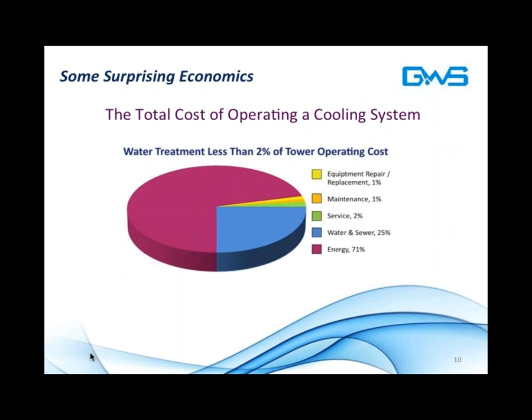You can see here that on average, water treatment costs less than 2% of the tower operating cost. So the big chunk of operating a tower in terms of cost is both water and sewer, 25% there in the blue section, and energy cost, about 71%. So we have a significant opportunity in front of us to improve the efficiency of our operating systems to cut overall cost. And that should be our focus. I would argue that every building manager and operator should make system efficiency a significant focus if they want to drive down costs. Said another way, focusing on the operating cost of chemical inputs is penny wise and pound foolish.